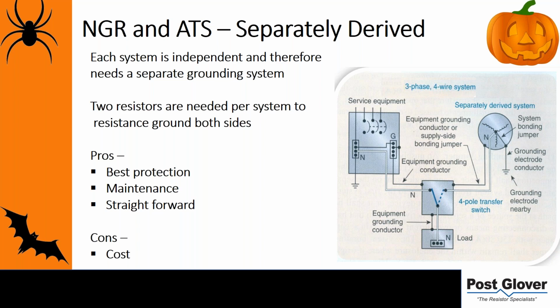The NEC talks about separately derived and non-separately derived systems. Separately derived just means you have two different systems, one on the utility service and one on your backup or emergency generator, and you switch between the two, completely separate. You switch the neutral and the three phases, so you need a 4-pole transfer switch. Since there are two separate systems, that means two separate grounding systems. We recommend it this way because it's the most flexible and has the least problems, but it does mean that if you want resistance grounding on both sides, you need two resistors because they're separate.